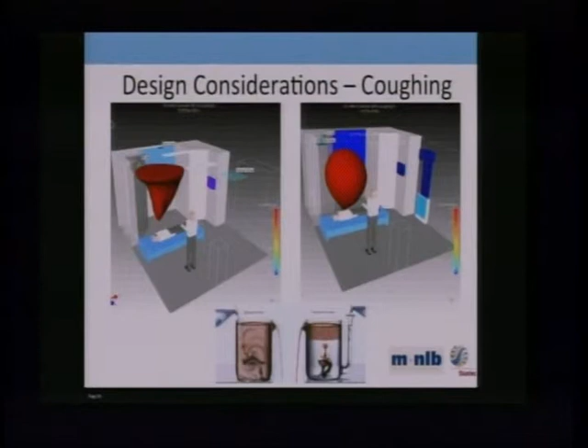That's on the left, an overhead mixing system at 6 air changes per hour. On the right is the displacement ventilation system, and you can see through this beaker that the supply air is supplied low, and the natural piston effect moves the air to the top, and it's exhausted high.